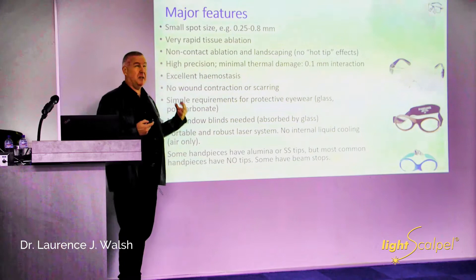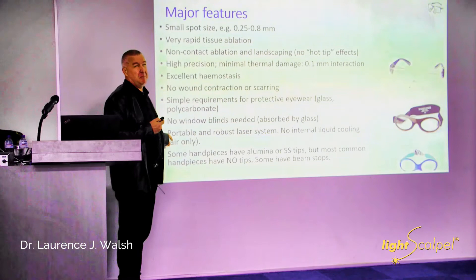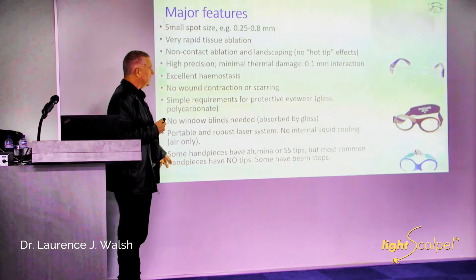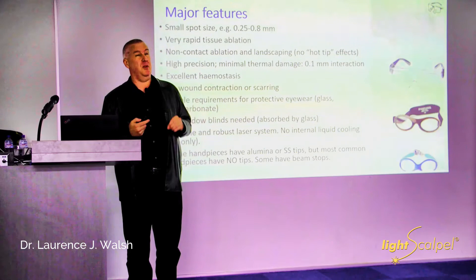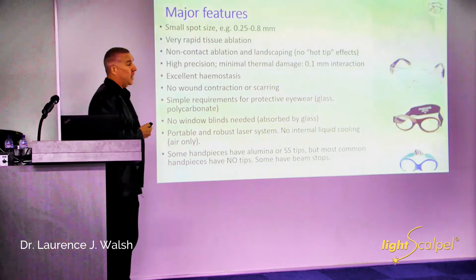Under the 2018 Australian Standard 4173, you don't need window blinds for a CO2 laser because glass absorbs it. You can pick this laser up — it doesn't make much noise because it hasn't got a big complex heavy cooling system. The handpieces have some really neat features, including idiot-proofing features like a beam stop, so you cannot blast through someone's uvula and hit their posterior pharyngeal wall — which if you're doing surgery around the soft palate is a really good thing.